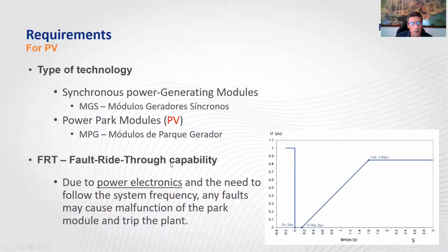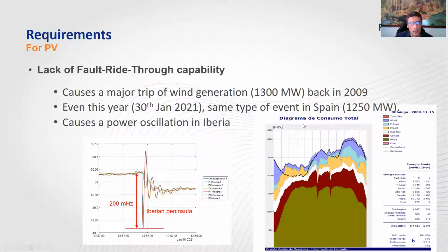One of the major requirements related to power electronics is the fault ride-through capability, since when we have faults in the grid, we have voltage dips, and normally if the plants don't have this capability, they tend to trip, okay? And this, of course, is bad for the system, because we need the generation to supply the load, okay? In the past, we had issues.